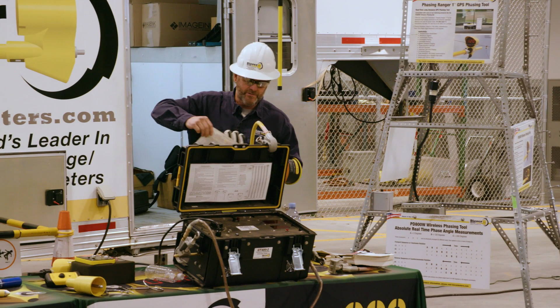So in OSHA 1910.269, go to lowercase n, talking about your temporary protective grounds, like elbow ground, cluster ground, whatever. When it talks about your grounds, go to number 5, and it tells you that before you install your TPGs, you're going to use your tester and verify an absence of nominal voltage, correct? Right? Absence.